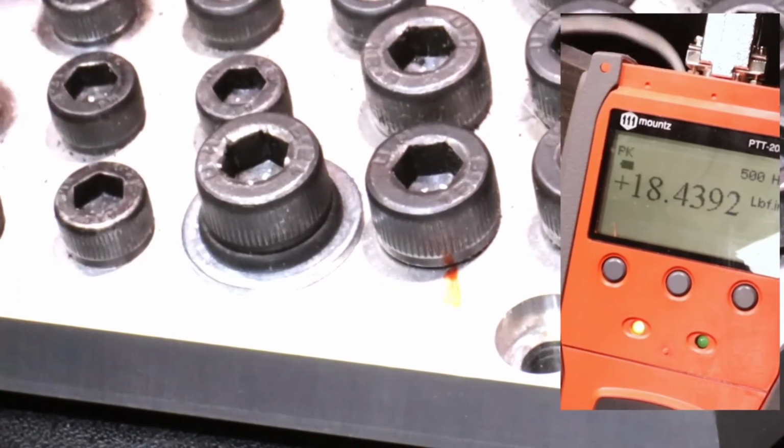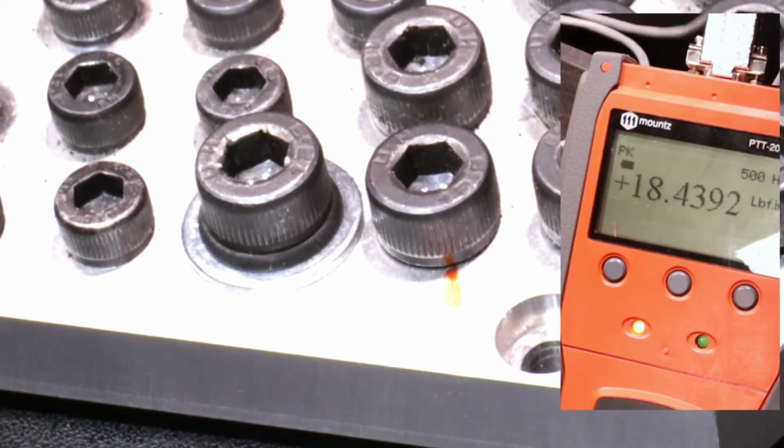And so again, depending on the different characteristics of the particular joint, this is a way for us to develop a correlation between what we are seeing when the tool is performing and what we see when we test. And we could develop parameters so that if we are doing after-assembly audits, we can make sure that a value that we may see that may be different from the actual value that was produced is still within an acceptable limit based off of sample data that has been taken.